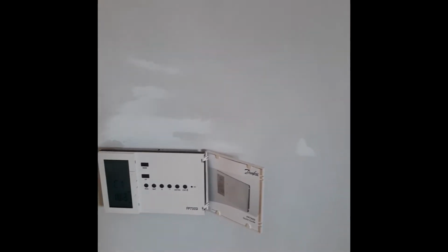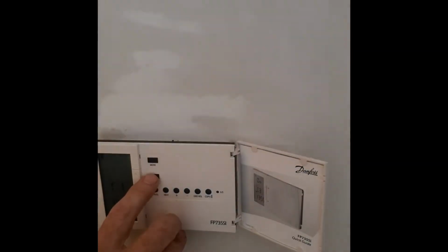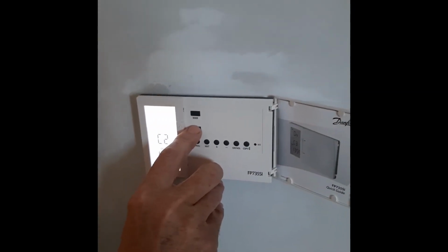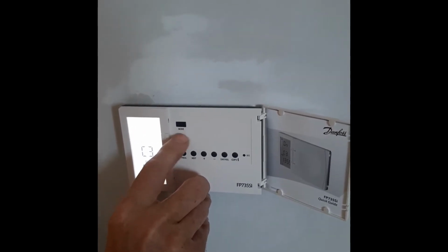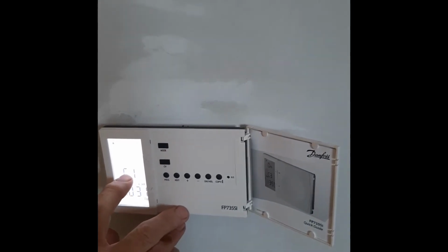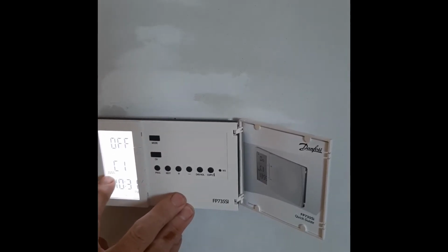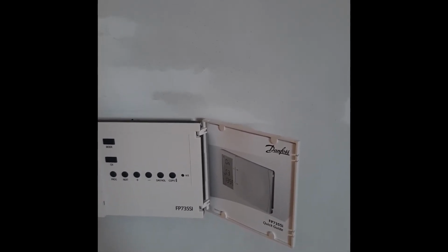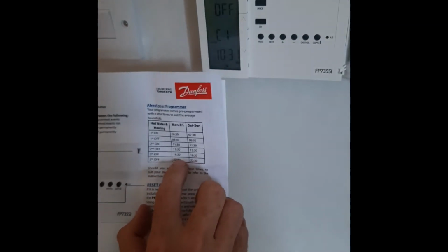So basically, this is your channel switch for changing channels. There's channel 1, which is downstairs heating, channel 2, which is upstairs heating, and channel 3, which is hot water. So when you go back to channel 1, these are the modes. To get this in a certain mode which suits you, you go there. That's 3 ons and 3 offs, which are preset. So Monday to Friday, 6:30 to 8:30. The second one comes on at 11:30, goes off at 1:30. The third one comes on at 4:30 and goes off at 10:30.